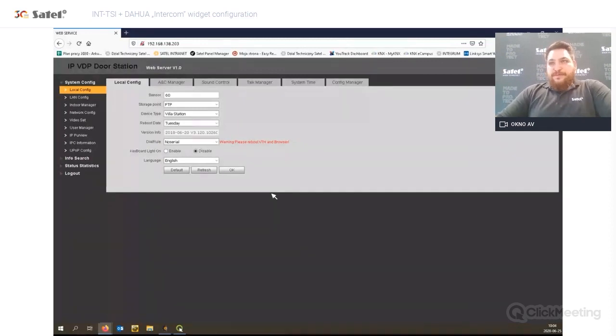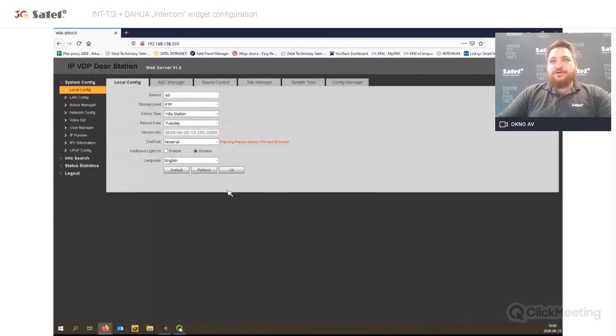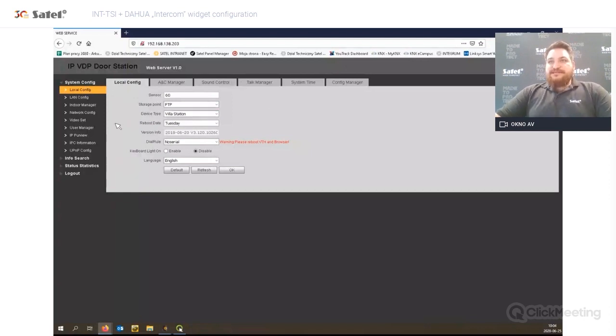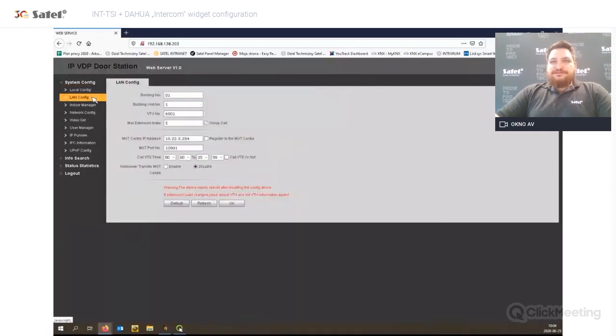What is important about the door station: we are using the Dahua protocol to integrate, so you need to use the video door station with the Dahua protocol. At the moment, SIP is not possible to connect with the INT-TSI. About the settings from the door station, the thing we need to set is the VTO number. In our case we will use the factory setting, which is 6901 — this is the unique number of the door station.